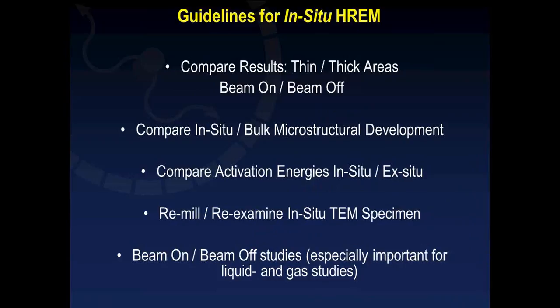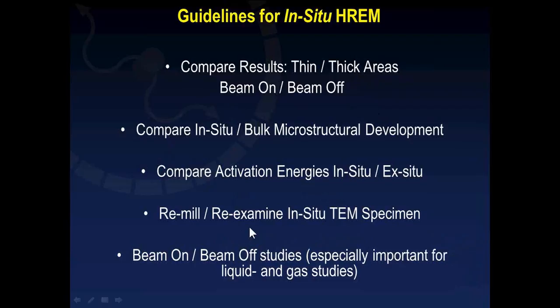Some guidelines developed for in situ TEM include: compare results from thin and thick areas of the sample; perform experiments with the electron beam on versus off to check for beam influence; compare in situ versus ex situ experiments by looking at bulk microstructure development and comparing activation energies. After in situ TEM experiments, you can re-ion mill the thin foil sample and re-examine new electron-transparent regions. The beam-on and beam-off studies are especially important for liquid and gas cell related studies.